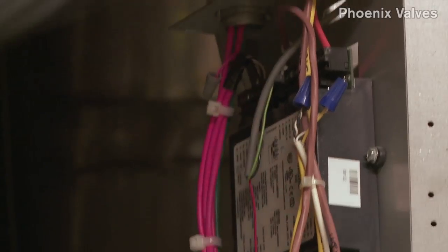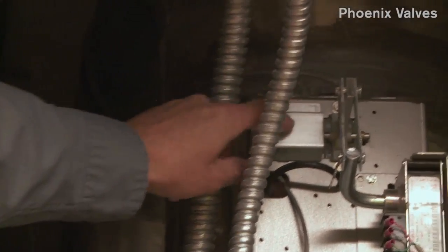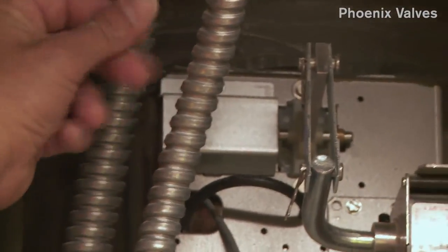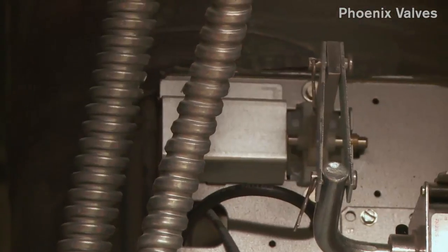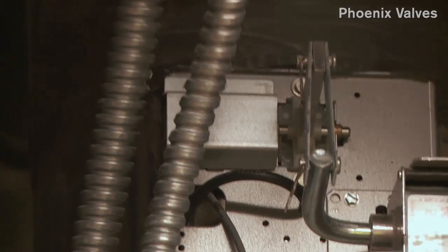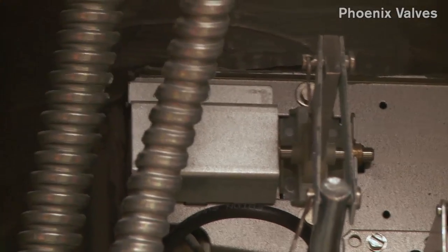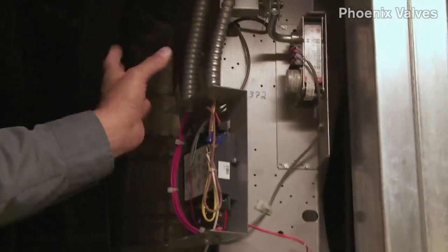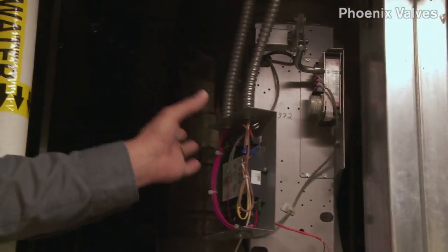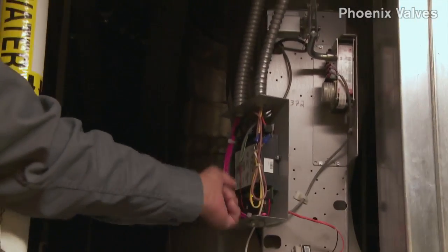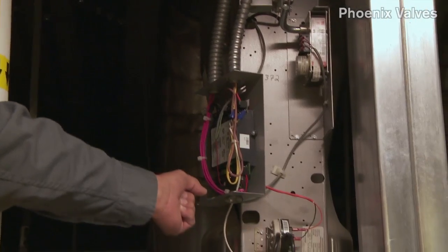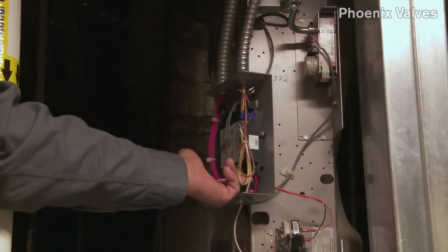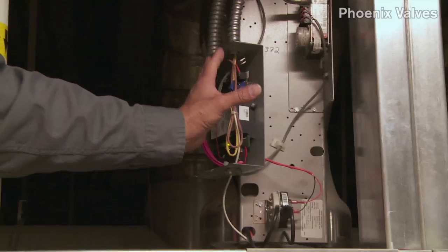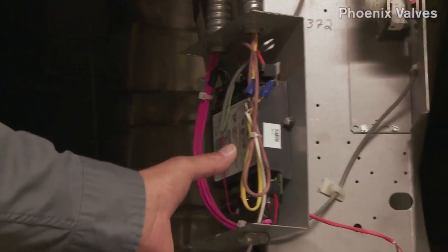You have your voltage potentiometer inside, underneath this cover. That's the potentiometer that's connected to the pivot arm of the valve. As that turns, it changes the resistance in the voltage. The resistance in the voltage on the board tells the board what flow feedback it has, and it's coming through a couple of wires that are on here. Your basic wires are just your power. On this one, it's an exhaust only card, so there's no tracking valve.